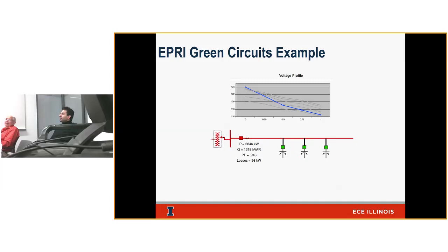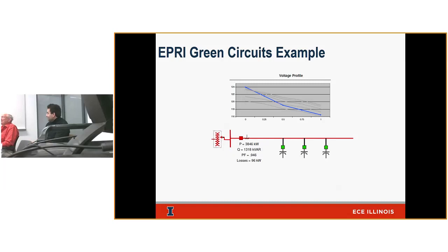The loads are forecasted or allocated along the feeder, so the losses are calculated with some error factor. You know the power factor at the feeder head; from a power flow you would know what the loads were, then compute the sending power. Using AMI would bring back 15-minute interval KW, KWH, and voltage, so you can calculate losses in real time. For this example, the power factor and losses are based on load flow using real-time P and Q.